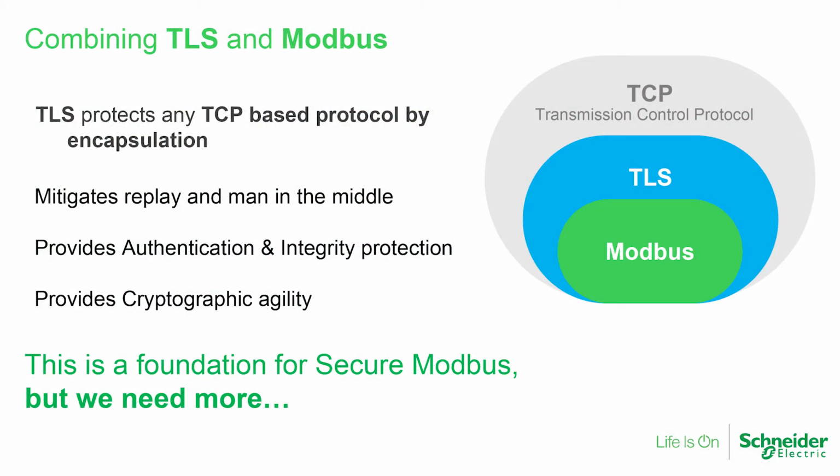And our problem becomes, how do we combine this with Modbus? Now, the good news here is that TLS can protect any TCP-based protocol just by encapsulating it. And what that already gives us is the foundation of communication security. We'll get mitigation for replay, we'll get mitigation for man in the middle, and we'll get integrity protection. And if we want to have authentication, we'll have to do a bit more, and we'll see how that will work.